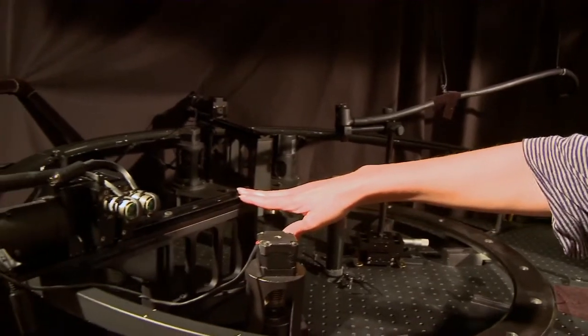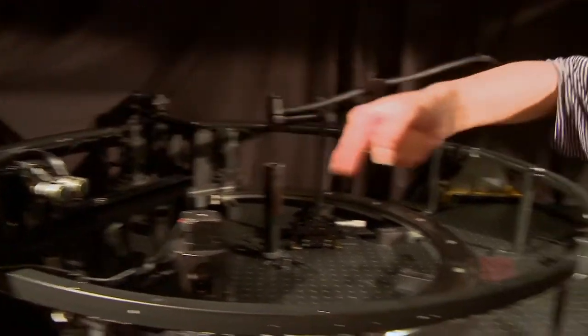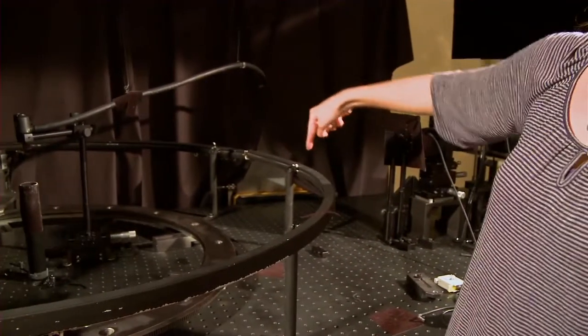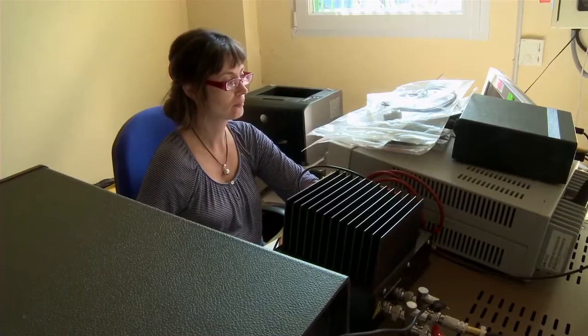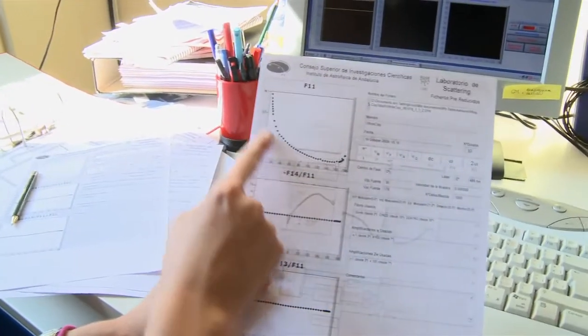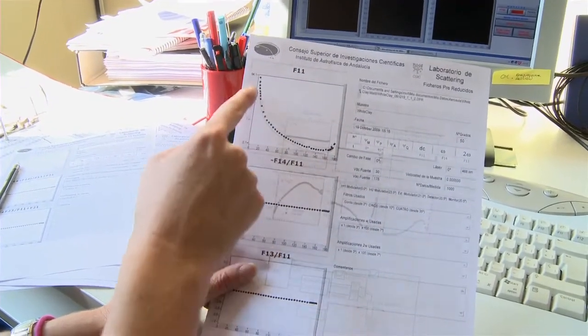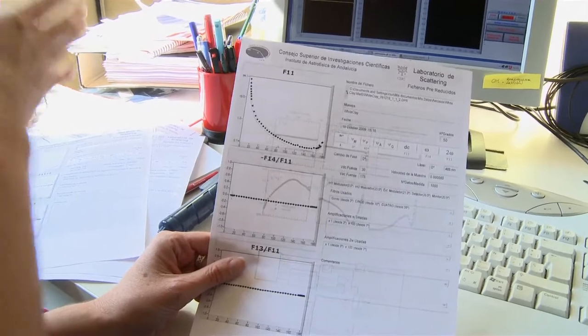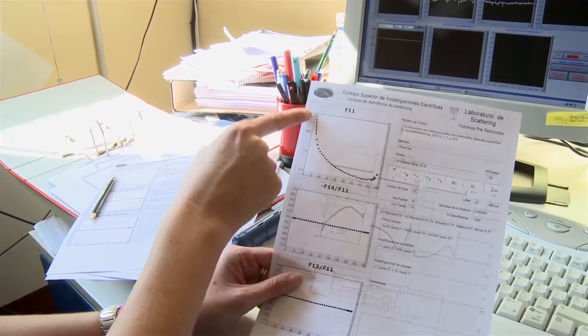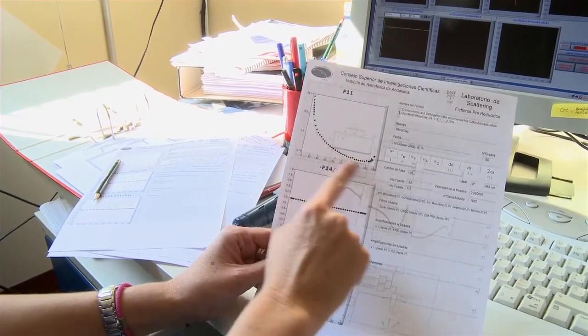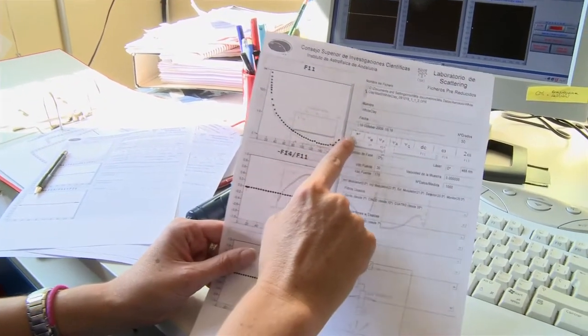The scattered light is detected by this photomultiplier tube that moves along this rim from positions close to the forward direction, moving all the way around to positions close to the backward direction. So this is the phase function — it's the angular distribution of the scattered light. We see that in the direction of the laser, the intensity is at maximum, and it decreases at outside scattering angles, and then it goes up again.